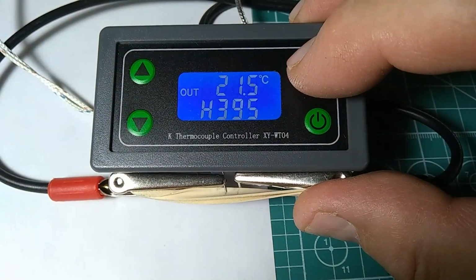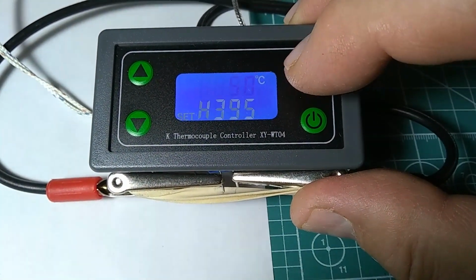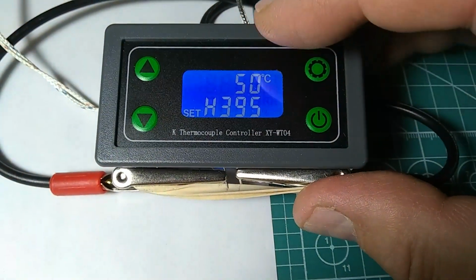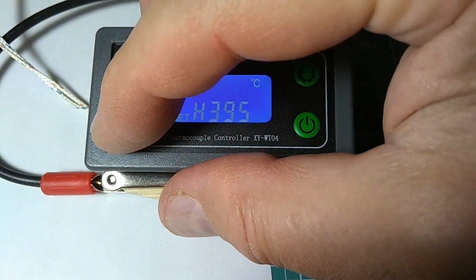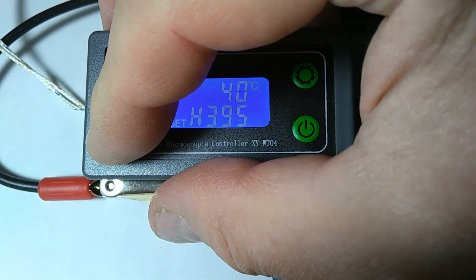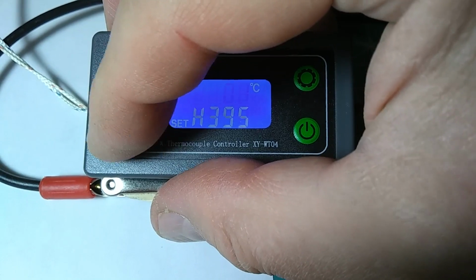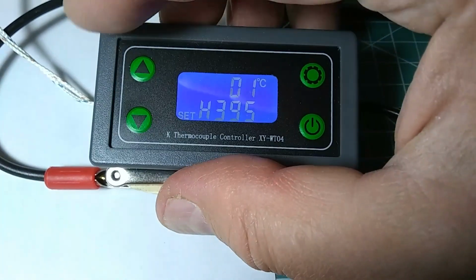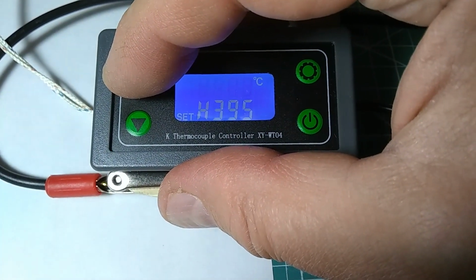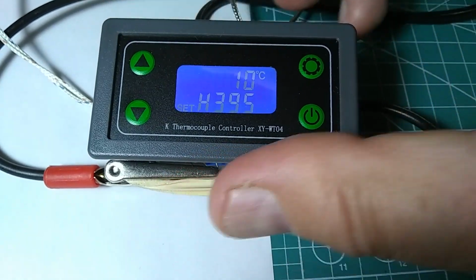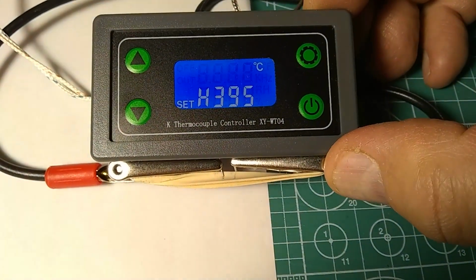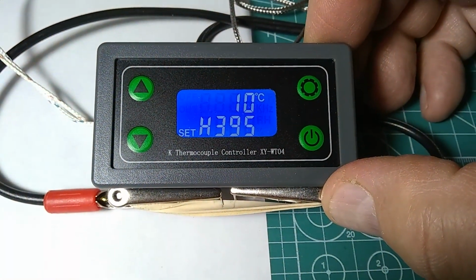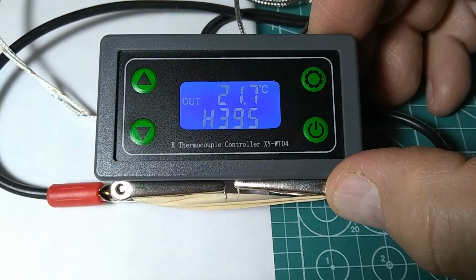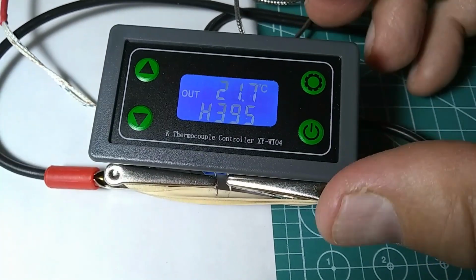If you go 3 times, it will be the hysteresis. Right now it's 50, which is the maximum, but you can go down to 1 degree Celsius, and this is the minimum hysteresis. And hysteresis is the difference in temperature between the set temperature and the temperature where the relay will go on or off.